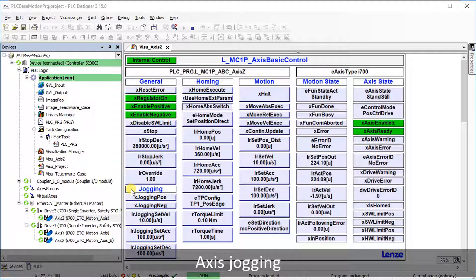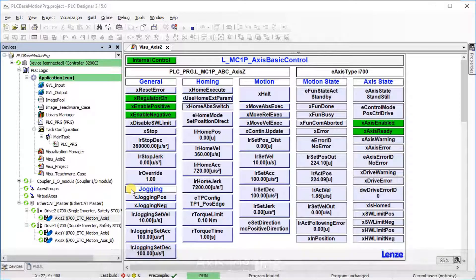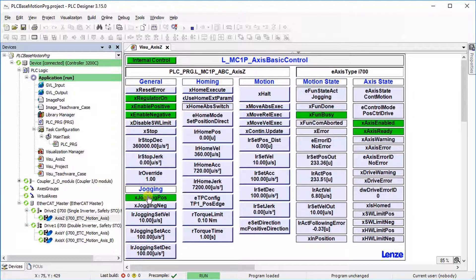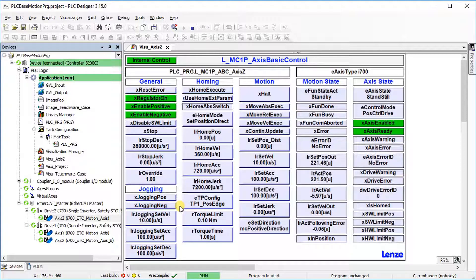Manual jogging can be done using this visualization. For manual jogging of the axis, jogging set velocity, jogging acceleration, and jogging deceleration are used. If jogging positive is true, the axis is traversed in positive direction. If jogging negative is true, the axis is traversed in negative direction. The axis is traversed as long as the input is set to true. The parameter values can be changed during operation and are accepted when the jogging positive and jogging negative inputs are set to true again.